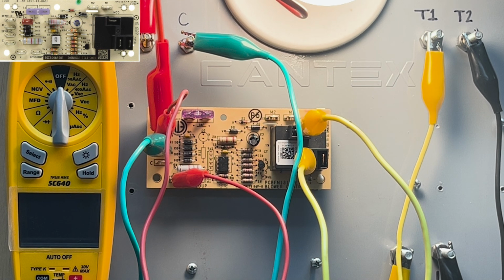Before I do that, I want to show you the off delay, because it's real easy to misdiagnose these if you have a board stuck in the closed position where the relay is just constantly energizing the motor, and you're trying to figure out if your board is good or bad.